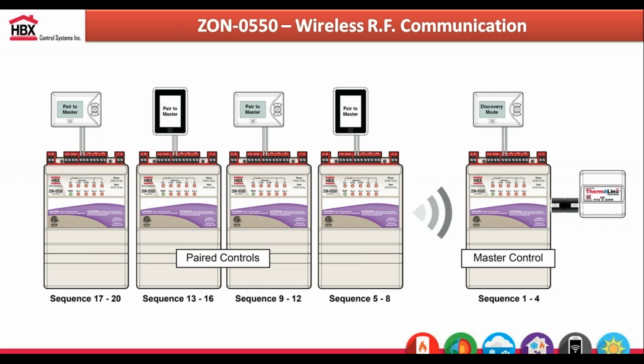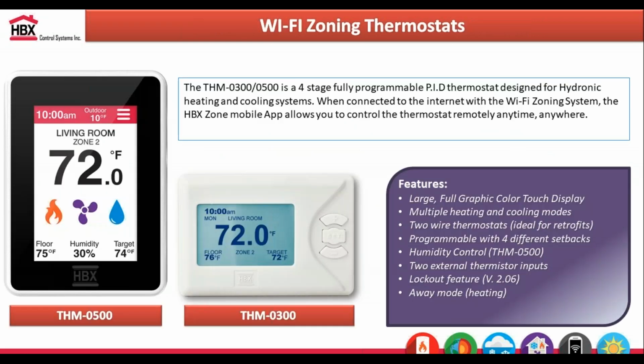If you have separate mechanical rooms, or you want to have a zone controller in each, they don't have to be right beside each other. You can have different zone controllers throughout the mechanical room. Or, like I said, you may have one mechanical room on one floor and another on another floor, and you want to make sure you have priorities, so you can pair them to each other without wiring them or daisy chaining them together, which is real nice.